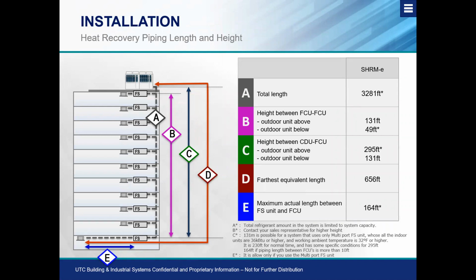With our heat recovery piping lengths, and also with our heat pump, again, we have our own software, so we don't have to remember these numbers off the top of our head. While they are nice to have as a quick reference, that group selection software has these numbers built in, so as you guys are working with us laying out a job, you can rest assured that we've met our minimums and haven't exceeded our maximums. And as a general rule of thumb, total piping length is 3,280 feet to achieve a carrier heat pump.